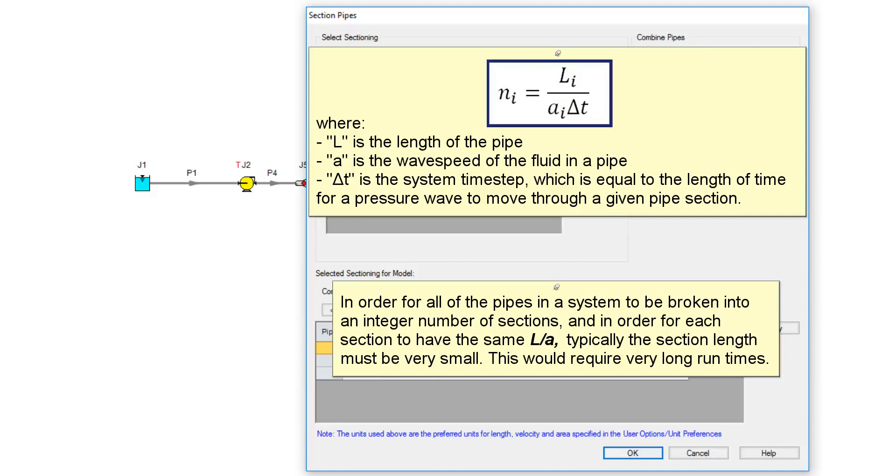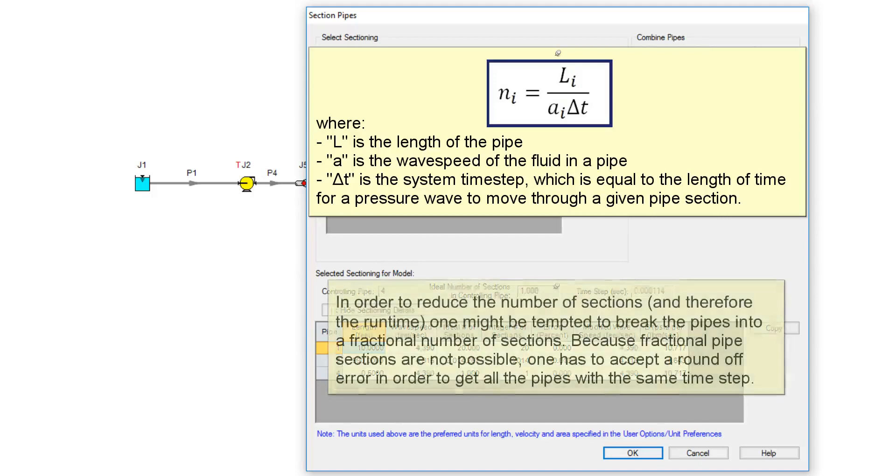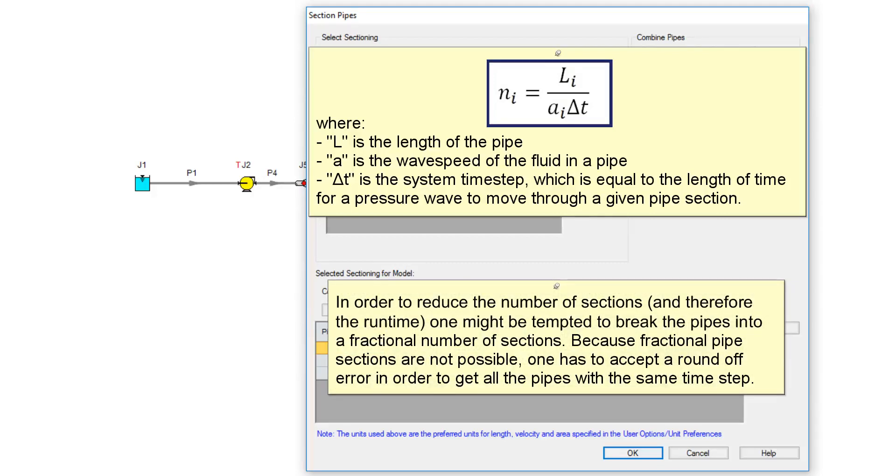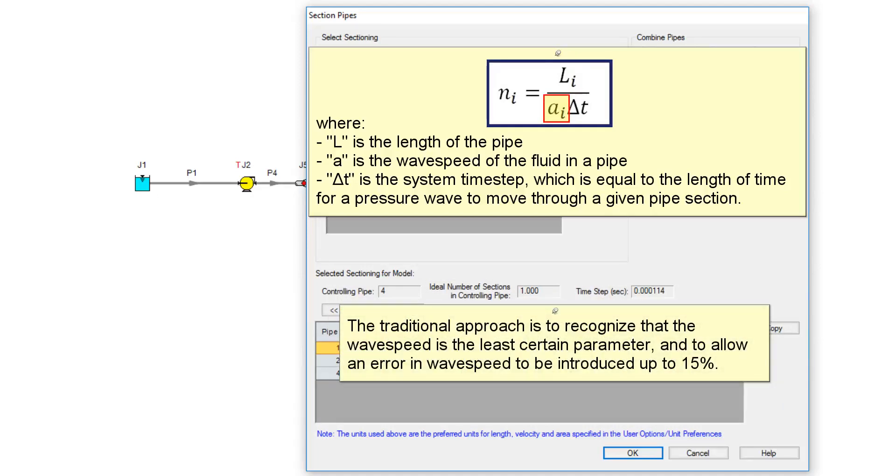In order for all of the pipes in a system to be broken into an integer number of sections and in order for each section to have the same L over A, typically the section length must be very small. This would require very long runtimes. In order to reduce the number of sections, and therefore the runtime, one might be tempted to break the pipes into a fractional number of sections. Because fractional pipe sections are not possible, one has to accept a round-off error in order to get all the pipes with the same time step.